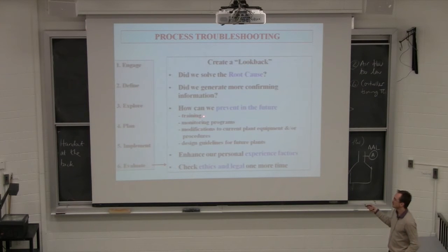Training. Retrain or train your operators to avoid a protocol where they can create a dangerous situation from occurring. Monitoring programs require sensors, they require computer coding and it's trivial for me and you to say well just put a line of PLC code in there but it's not like that. When you just put a line of PLC code in there it's signed off by two or three managers, it has to be validated, check that it actually works. It can often turn into a week's worth of work for multiple people. Modifications to the plant and equipment. Now you're seriously pushing your boss. Oh, I want you to modify the process, I want you to modify the equipment. That almost certainly isn't going to happen but this is what we're aiming for and striving for and you would certainly do this for very critical safety issues.